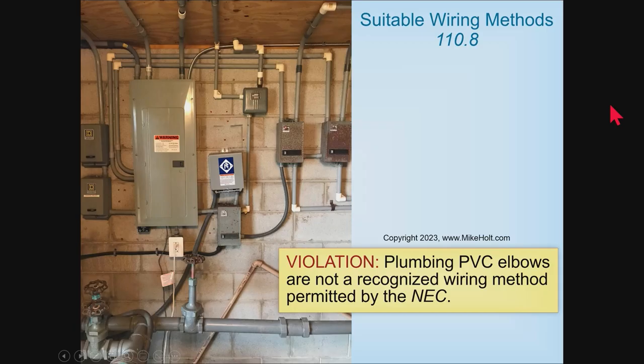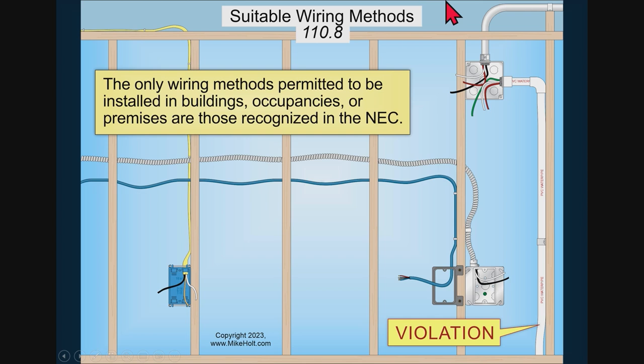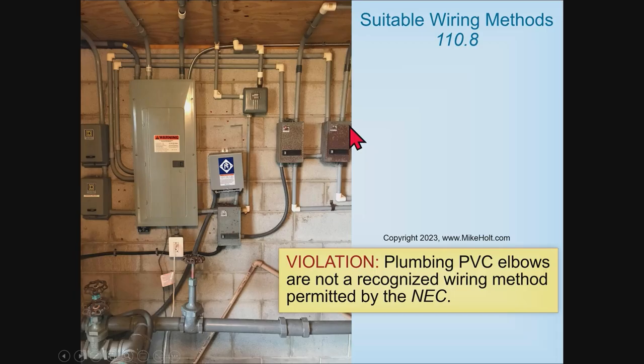Because of examples like this, it would probably be a great graphic to have in the book. If the rule says only wiring methods recognized by the code can be installed in buildings, occupancies, or premises, clearly these fittings are not recognized. It might be electrical piping, but the fittings are not recognized. And that's not somebody's house — that's in a commercial building. It's not like some homeowner went to Home Depot and bought some parts; that's on a commercial building.